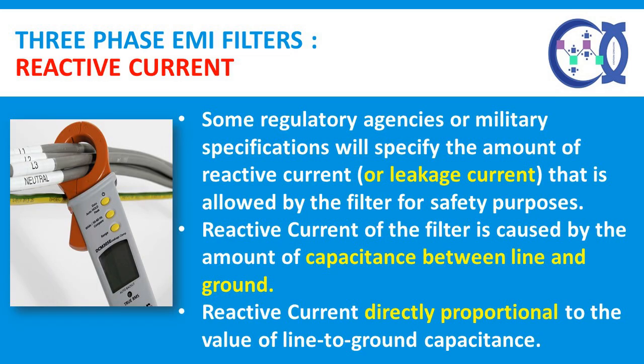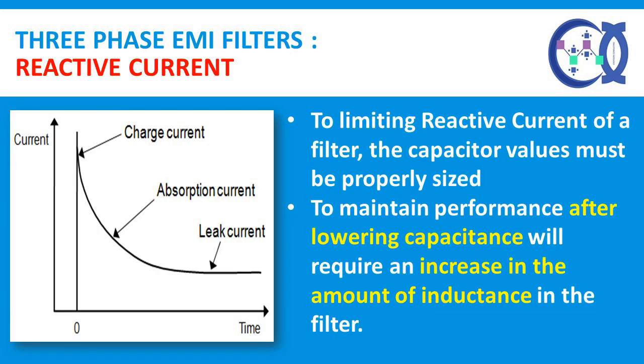This frequency range should be accompanied by the desired insertion loss or performance of the filter throughout the frequency range, in decibel. Reactive or leakage current — some regulatory agencies or military specifications will specify the amount of reactive current, or leakage current, that is allowed by the filter for safety purposes. Reactive current of the filter is caused by the amount of capacitance between line and ground. Increases in the values of the line-to-ground capacitance will cause the reactive current to increase, while decreases will lower reactive current. In order to limit reactive current of a filter, the capacitor values must be properly sized. Lowering the value of the capacitors will be detrimental to the performance of the filter. To maintain performance after lowering capacitance will require an increase in the amount of inductance in the filter.